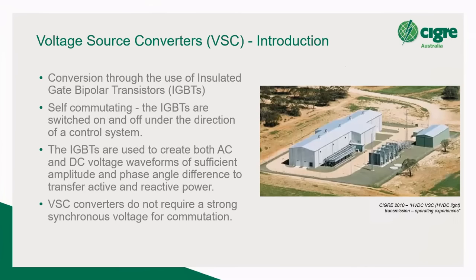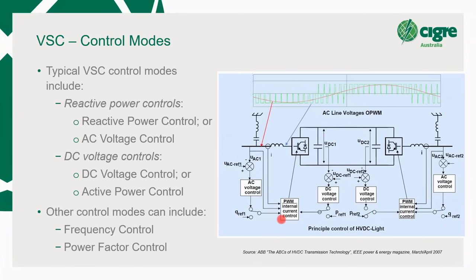Okay, so I'll just fast forward to that. Here we go. So the Q ref, these are actually operator inputs. If you're in reactive power control, then it's up to the operator to decide what reactive power level you would like. Think of it as kind of the switchable portion of a STATCOM. If you had a STATCOM with a switchable capacitor bank, and you want to offset it, so maybe you may want to use it in that way, where you set it at a value and you let some other device control your voltage.